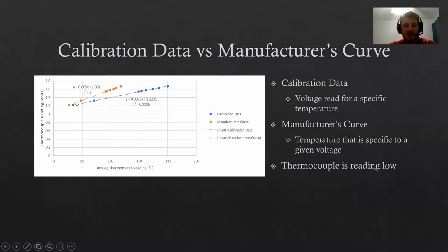The manufacturer's curve is the orange curve. That is the calculated values of temperature based on the read voltage. So that's provided by the manufacturer. So obviously we can see the thermocouple is reading very low. For freezing water, it's close. It's reading 1.2 volts and maybe around 30 degrees, or between 25 and 30 degrees Fahrenheit. But for the boiling water, it's the same voltage. Boiling water is reading around 130 degrees Fahrenheit, which is way lower than it's supposed to be. Boiling water is at 212 degrees Fahrenheit.